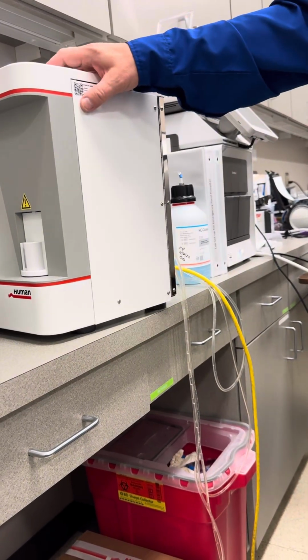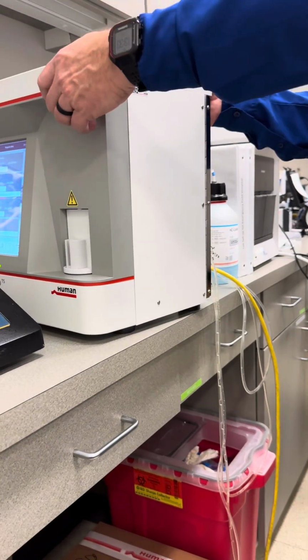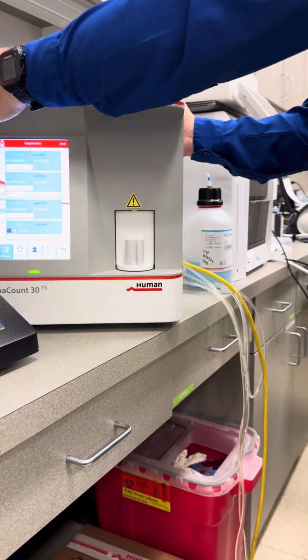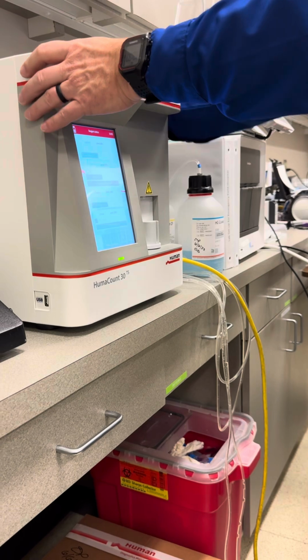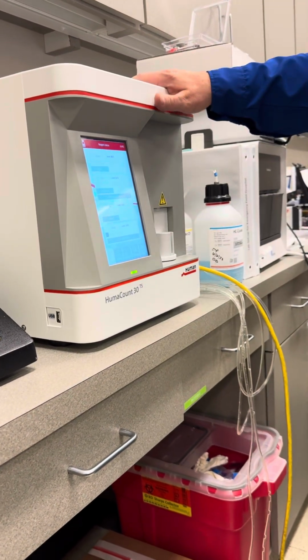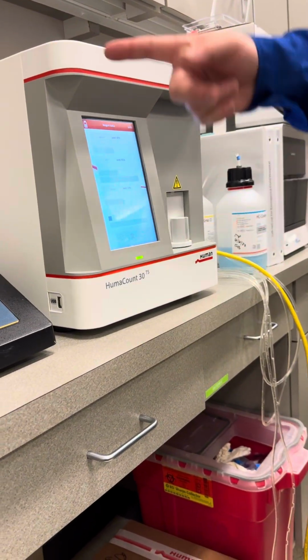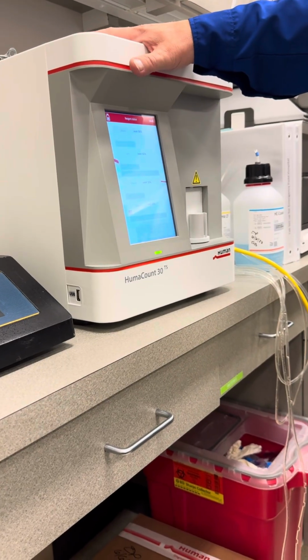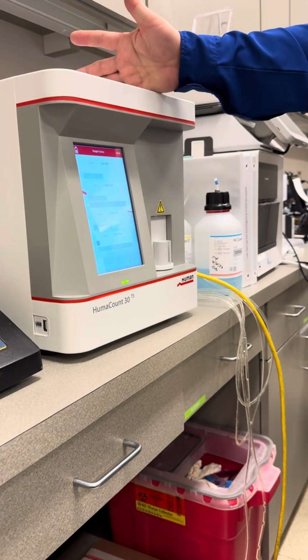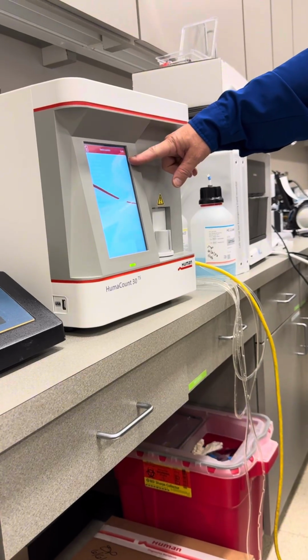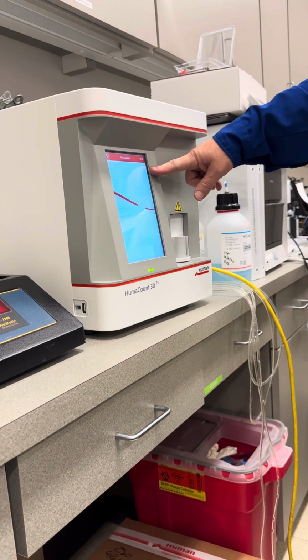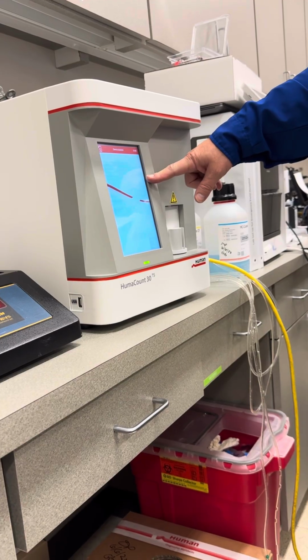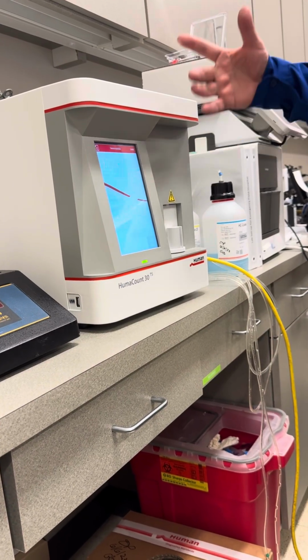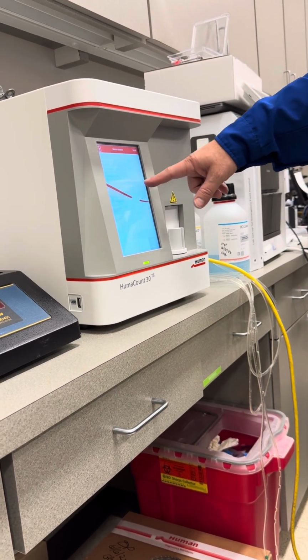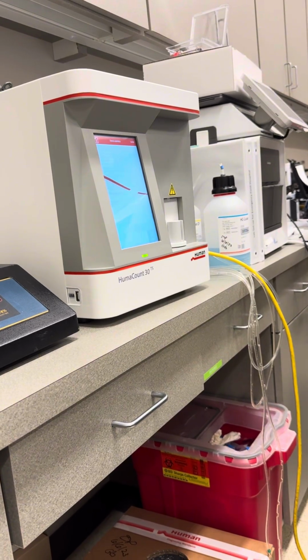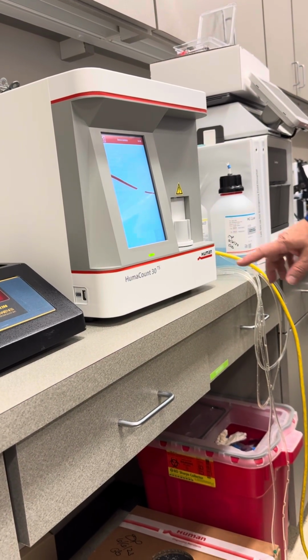Okay. It does state to use an enzymatic cleaner on it daily, whenever you start it up or are running it. It'll tell you to run an enzymatic cleaner. Okay. We've just been using a 10% bleach and running it through. The diagnostics screen is basically telling you how many diluent primes and lyse primes you've had, the number of measurements done on the instrument since it's been set up, vacuum errors, and your successful startups and shutdowns on it.